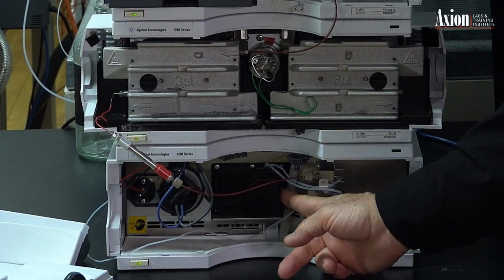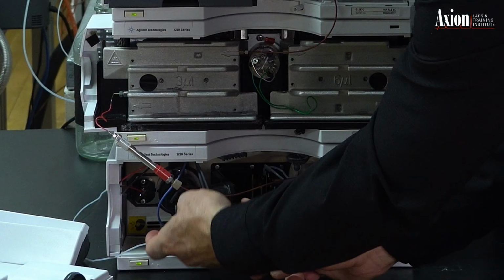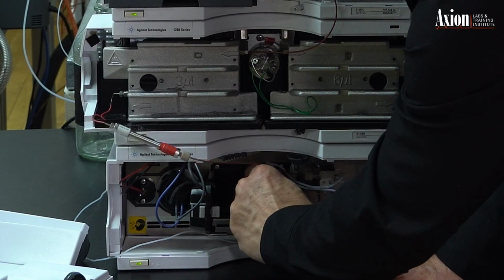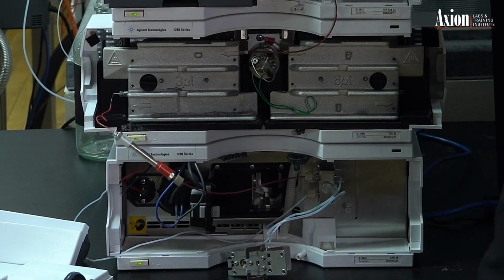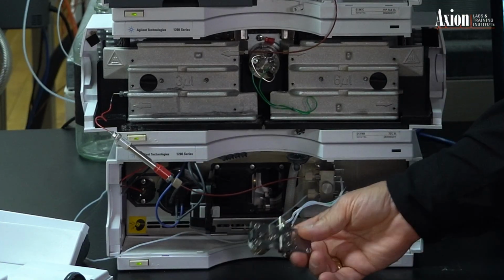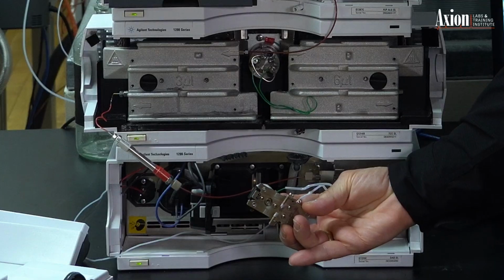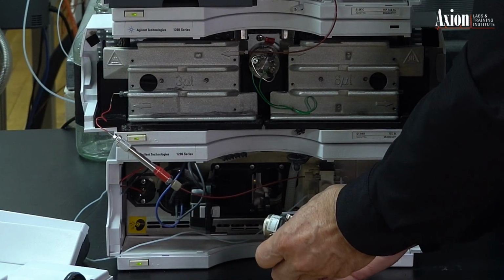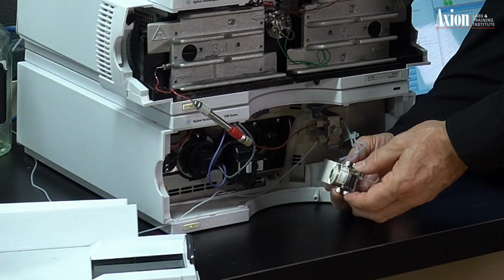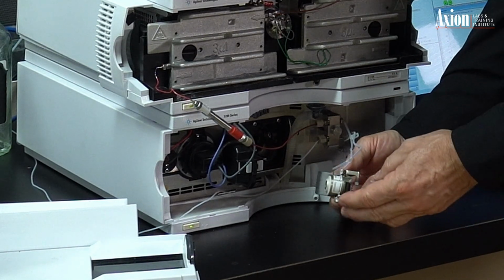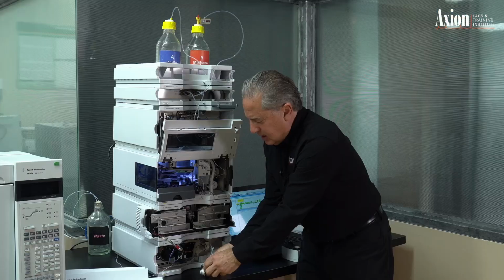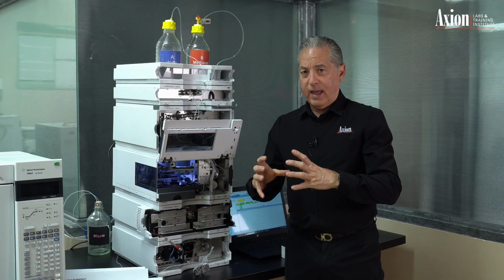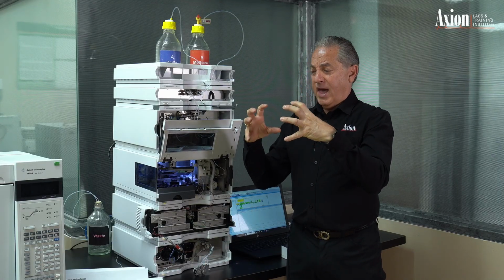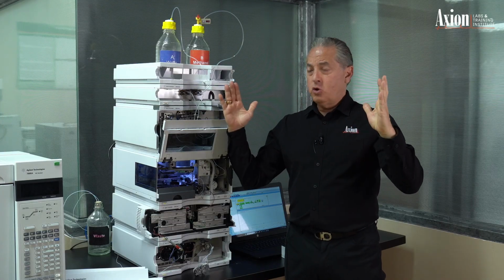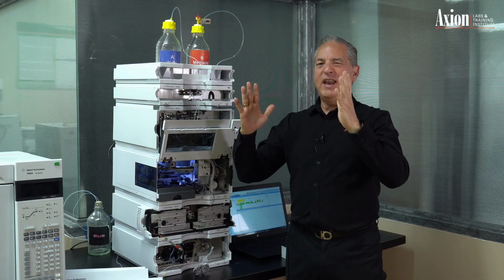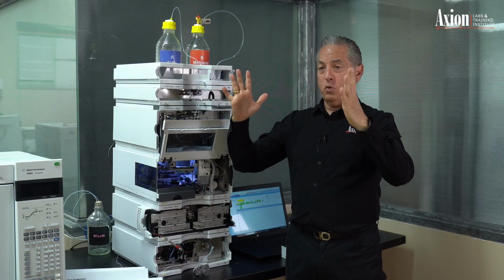So I could show you what it looks like. If I open up this little door, the flow cell itself is self-contained. So if I pull it out, there's flow going through the instrument right now. We're running a low flow rate, 0.2 mils a minute, but there's flow going through it, but nothing's going to come dripping out because this is a self-contained little piece. So if we look at it and try and understand the design, it's a really simple design. This detector cell is like a block of stainless steel, and we drill a hole in the middle, and we put 2 quartz windows on the outside. Not glass, but quartz, because glass absorbs UV light. So quartz windows on each side.